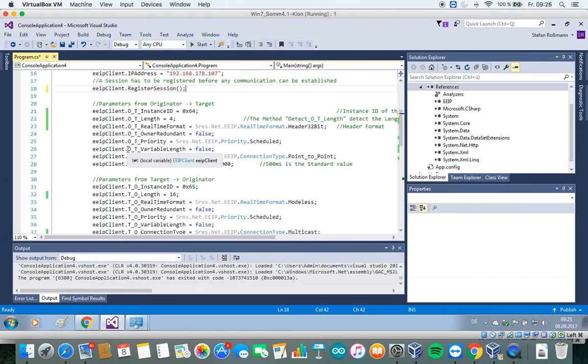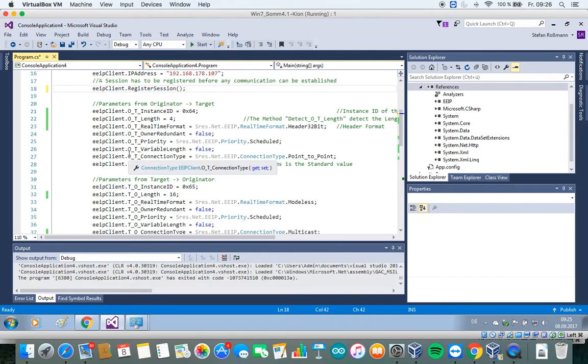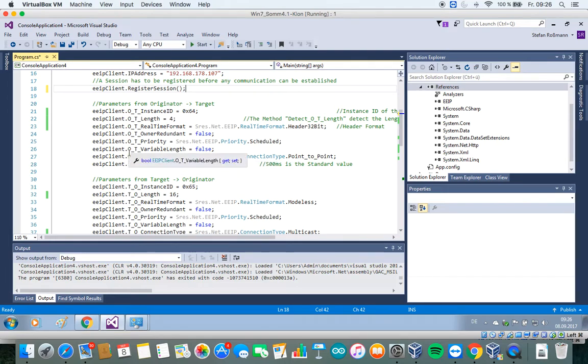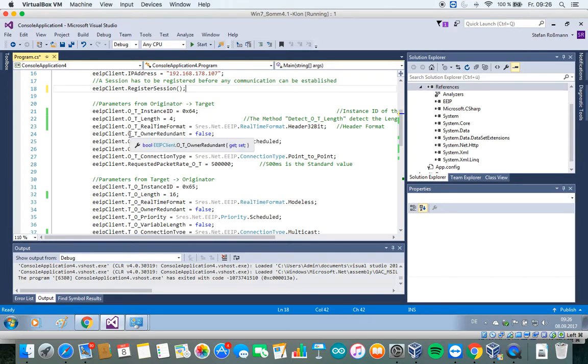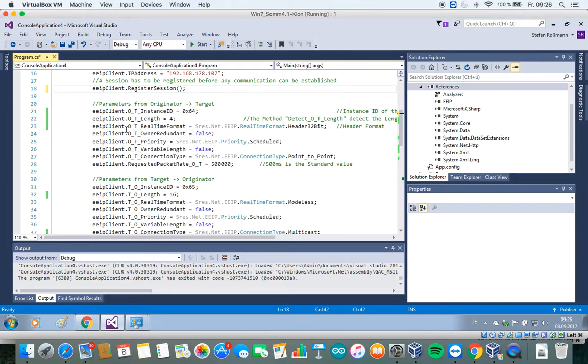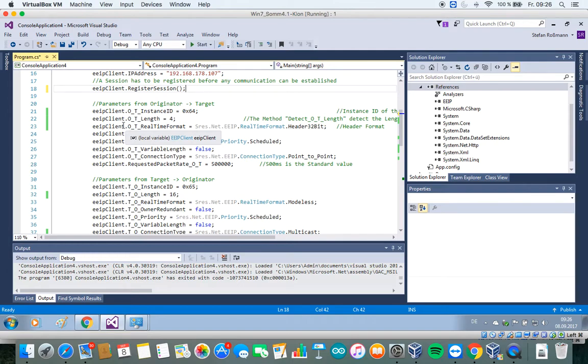We have to define some parameters which are only necessary for implicit messaging. That's why if it is possible, I would always recommend to use explicit messaging because it's a lot easier. There are some parameters which have to fit. Most of these parameters can be found in some documentation of the Ethernet IP device. I have to admit that the documentation of the Allen-Bradley device is not very good regarding the Ethernet IP settings.